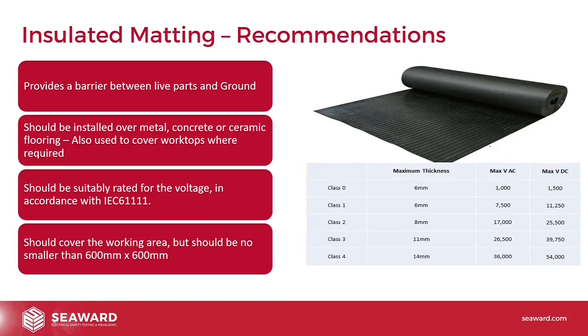Insulated rubber matting is really, really useful for both something to stand on and for bench topping. It provides a barrier between the live parts and ground, so we're isolating those parts from ground. It should be installed over any metal, concrete or ceramic flooring. It's really, really important not to test on those kinds of floorings. They're all very good conductors, really good at taking a charge from you or your equipment down to ground, and that's where the potential for shock lies. Also use it to cover the worktops where required.